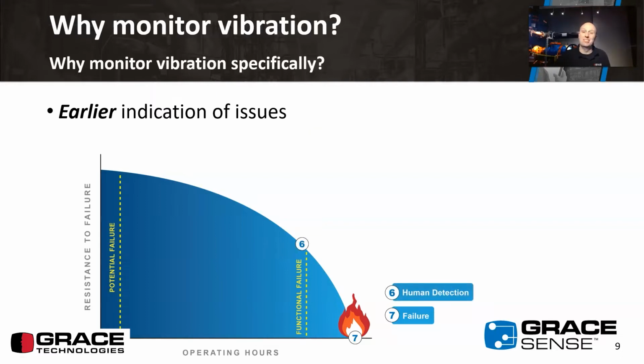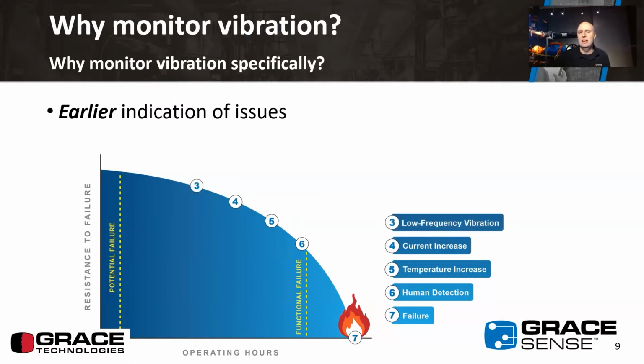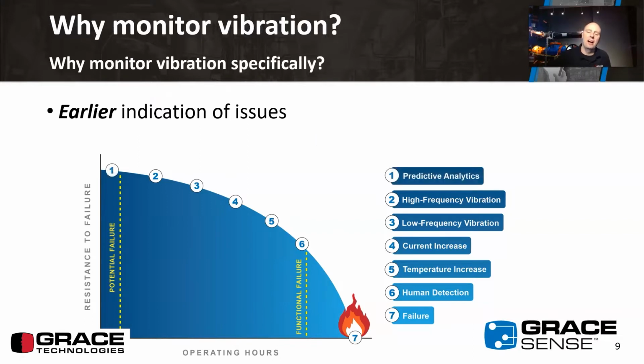If we're paying some attention and notice a piece of equipment starting to smoke or get louder, this human detection gives us a little bit of time, but not a considerable amount. Then if we start laying in sensing capabilities, like monitoring temperature or current, we see an increasing amount of forewarning before equipment fails. At number 3 on this chart, we get to what we're talking about today: low frequency vibration, then the higher frequency vibration spectra. At the very high end, we leverage all of these pieces to do predictive analytics.